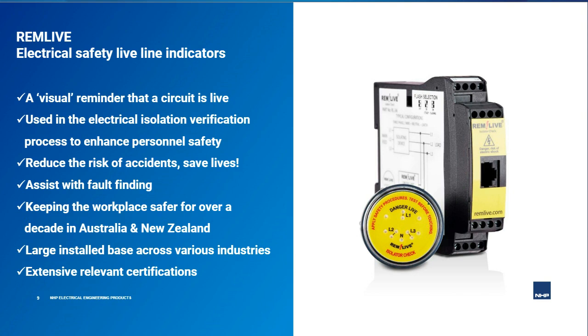If there's a problem, then REMLIVE can detect it. And as a result, this can help reduce the risk of accidents to the operator user and, importantly, potentially save lives. At least it's going to reduce the risk of accidents. The REMLIVE display unit indicates individual phase voltages on three-phase systems as well as the neutral. And this status information can be used to assist in identifying where those dangerous voltage levels are, even after isolation has occurred, if there's a problem like we heard about in the example earlier.